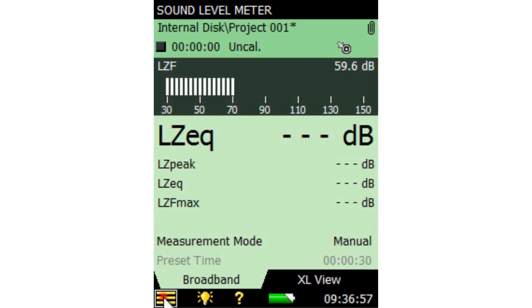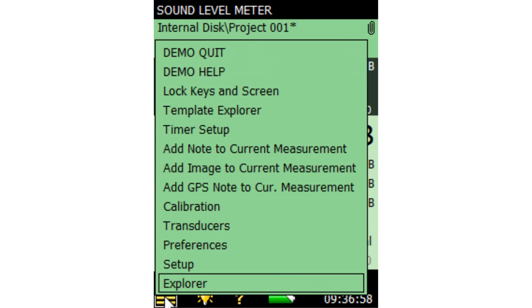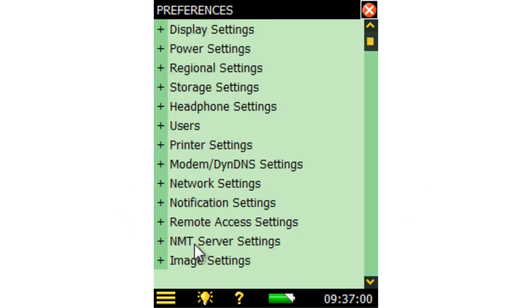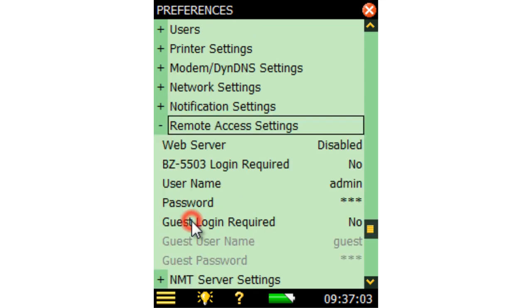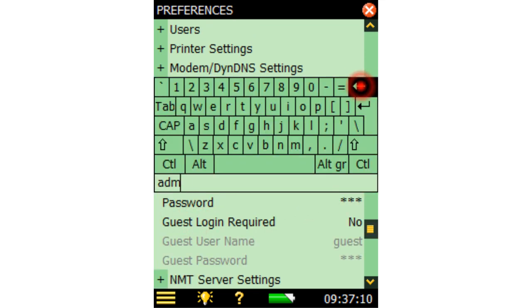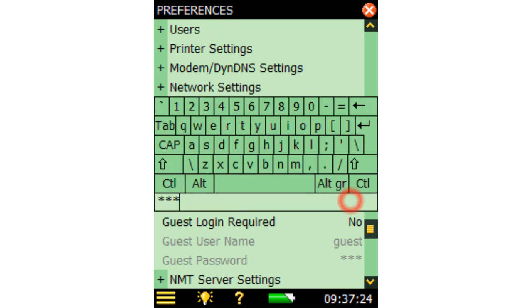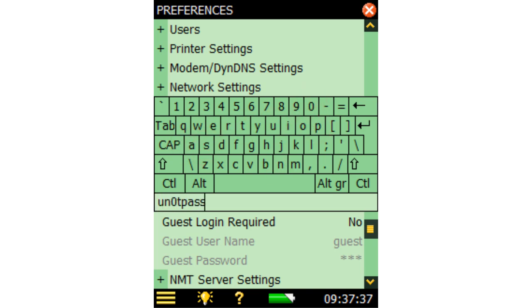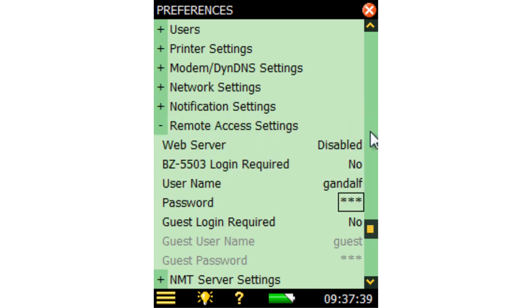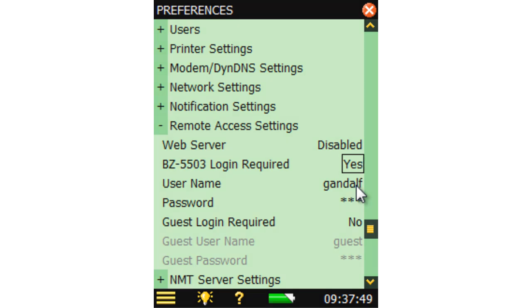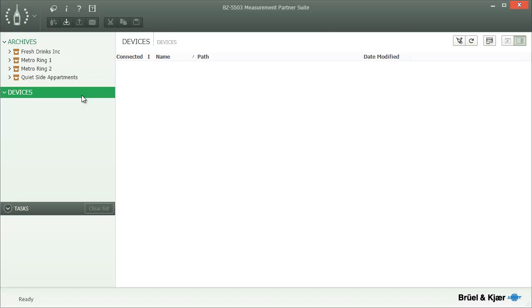To activate password protection on your instrument, open the main menu and select Preferences. Expand the Remote Access Settings group and set a username and password. The analyzer can then only be accessed over the web with the correct username and password. By setting the BZ5503 login required option to Yes, password protection will also prevent unauthorized access when connecting to the instrument from Measurement Partner BZ5503.